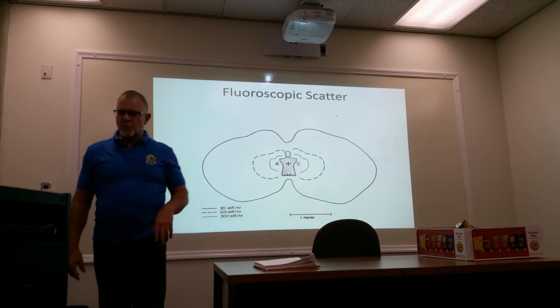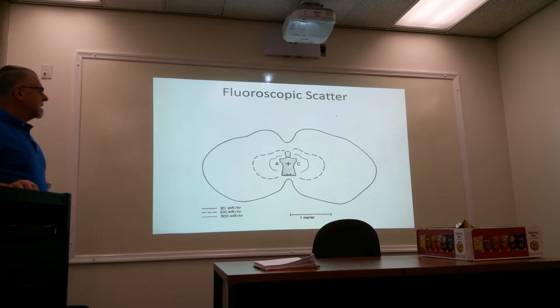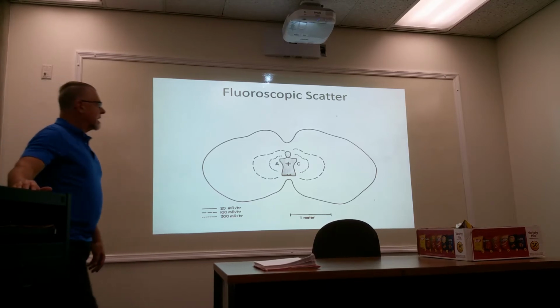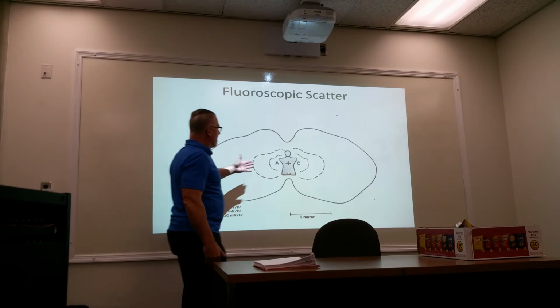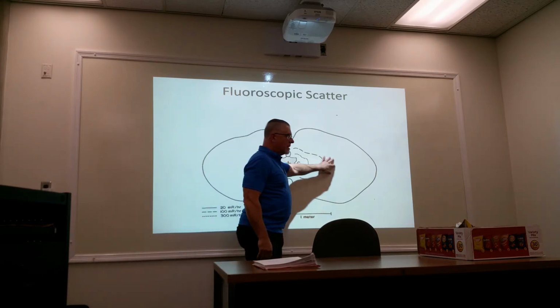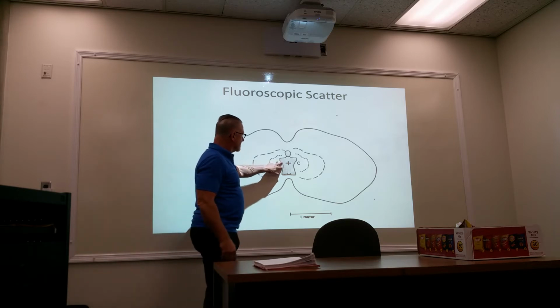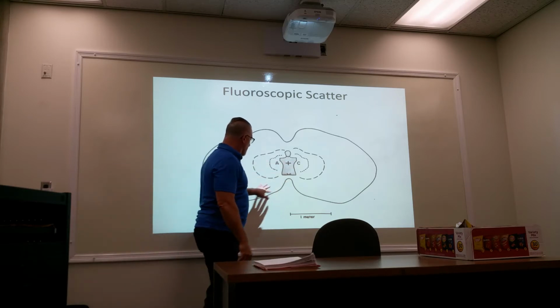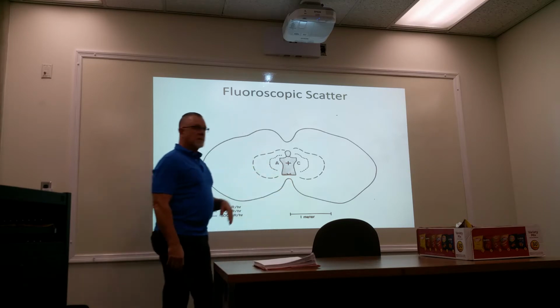These are the 20 mR per hour line, 100 mR per hour line, 300 mR per hour line. This is a research unit that allowed fluoroscopy at, I believe, 80 kVp at 10 mA. So it was a high output. You needed something high so that you could actually measure the exposure rate. The thing to look at is scatter distribution is related to the shape of what you're fluoroing. So for a body, it's thinner here, so if you're in the midline, obviously you're going to get more scatter because it has less tissue to go through, whereas here, you've got a lot more tissue, so it attenuates a lot more. That gives it that typical butterfly shape.